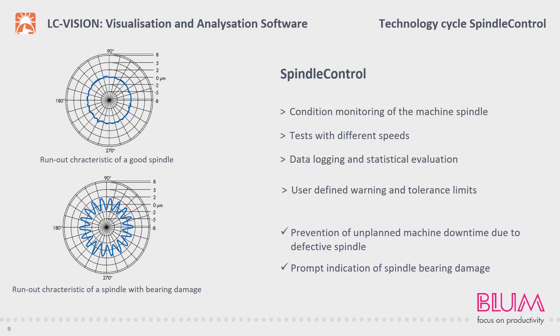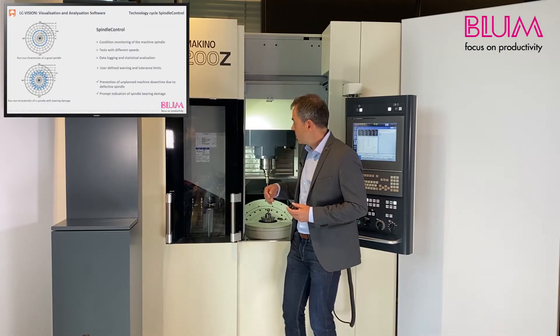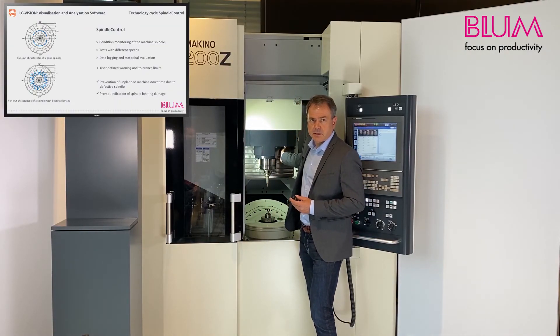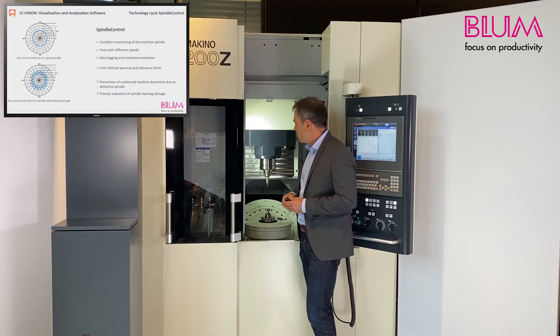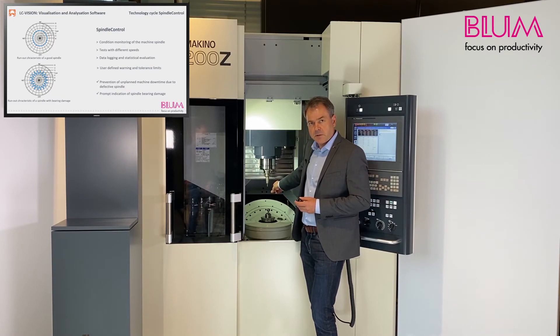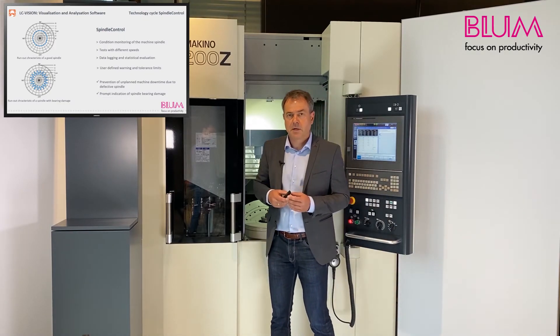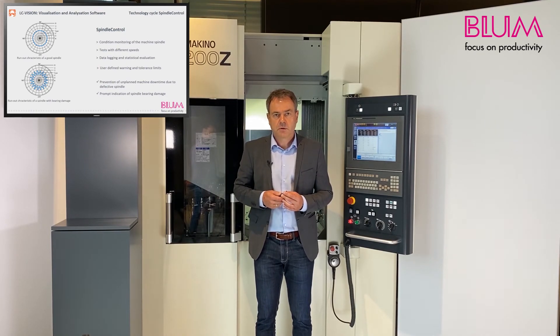We now turn our attention to the spindle control technology cycle. The ability to monitor the condition of the machine spindle ensures early detection of bearing damage and prevents unplanned machine downtimes caused by a defective spindle. Typically, the sensor system for monitoring the spindle is integrated in the spindle housing, which has the effect of attenuating the measurement. Spindle monitoring using the LC50 DigiLog is performed using a reference tool in the spindle and therefore directly on the rotor — in other words, on the exciter — and is therefore a more sensitive and informative sensor system. This means that vibrations can be detected earlier.